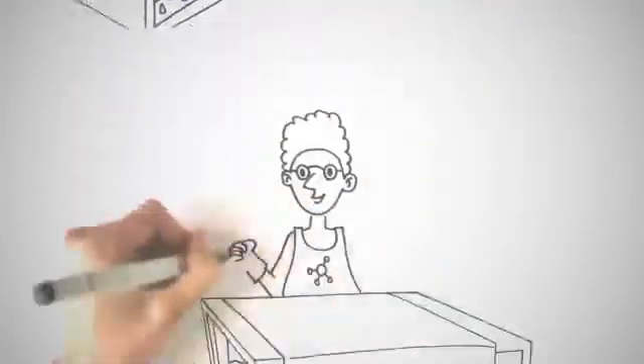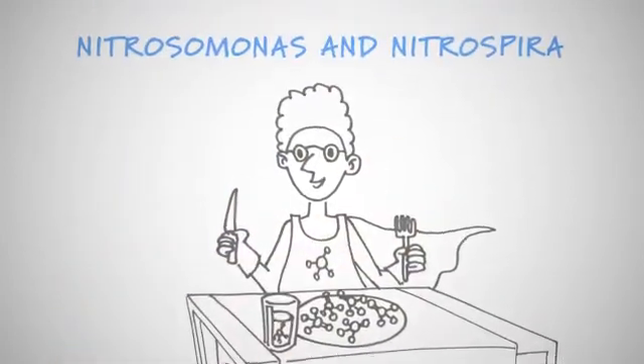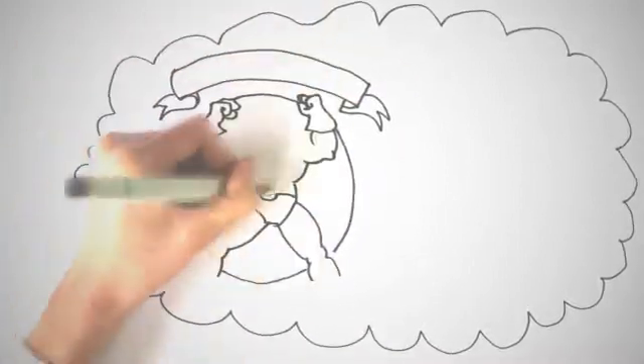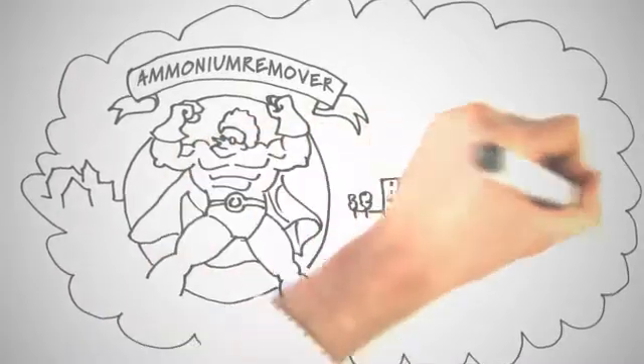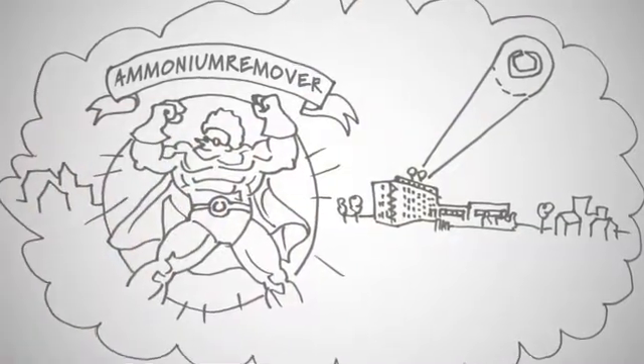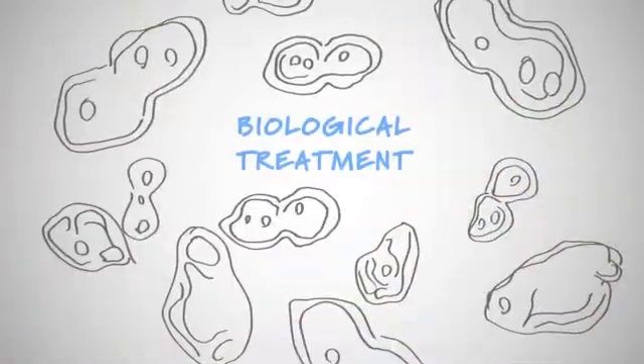We use bacteria to remove the ammonium. These so-called ammonium removers are good bacteria that eat up ammonium. In this way they help purify the groundwater, a process which we call biological treatment. The ammonium removers deal with the ammonium by turning it into nitrate. This takes away the disadvantages of ammonium.